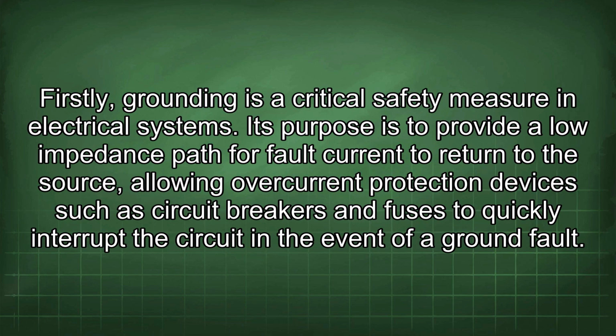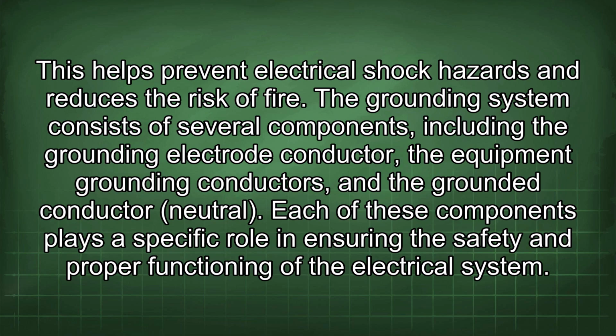Firstly, grounding is a critical safety measure in electrical systems. Its purpose is to provide a low impedance path for fault current to return to the source, allowing overcurrent protection devices such as circuit breakers and fuses to quickly interrupt the circuit in the event of a ground fault. This helps prevent electrical shock hazards and reduces the risk of fire.